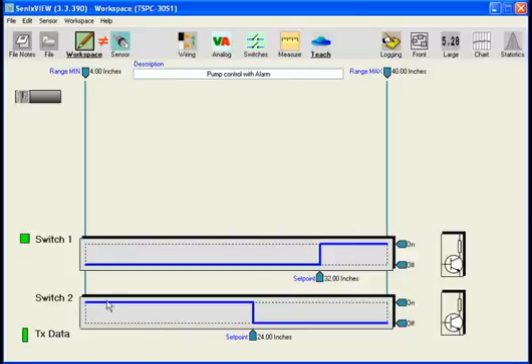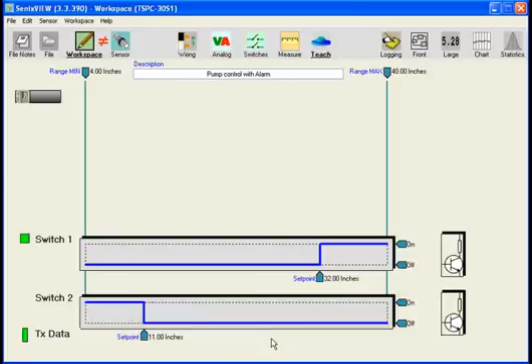Or you might set a switch for overfull to prevent overfilling. Let's let that happen. And you remember this window stops at 12 inches. The hysteresis. So let's just put it at 11 inches. For the sake of amusement, we will copy it to the sensor.